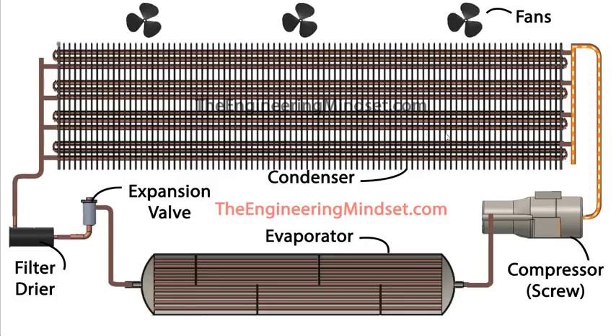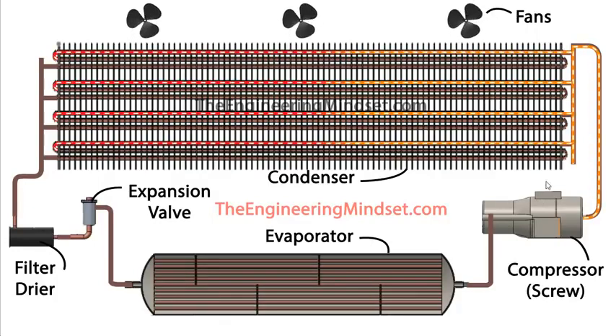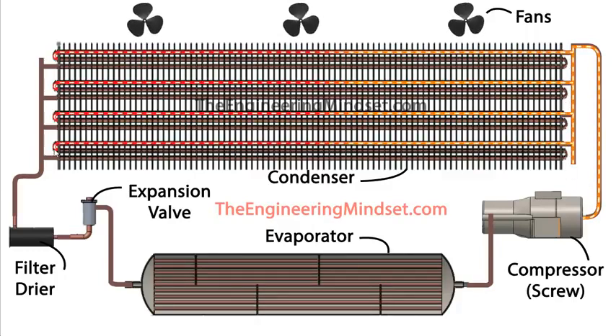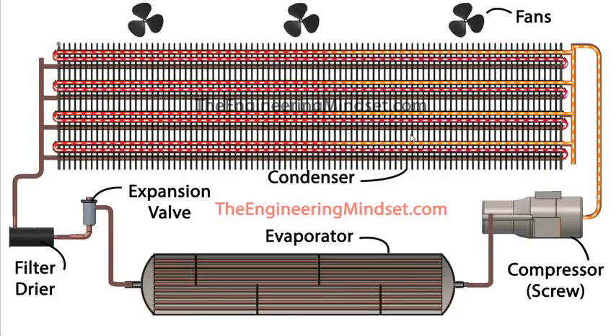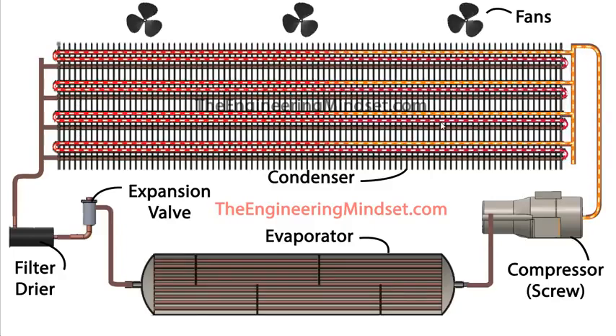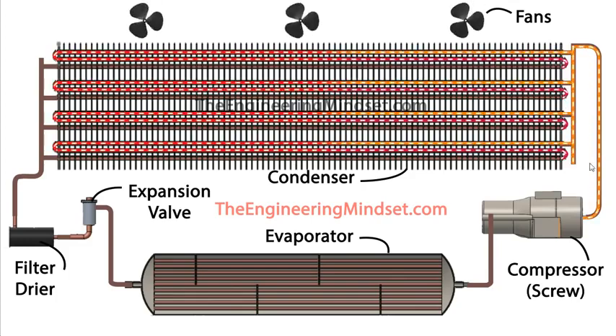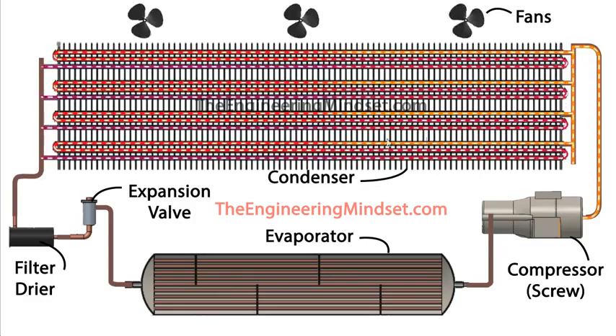These fins basically help to transfer that heat away from the pipes and out into the stream of the flow of air, so that increases the heat transfer surface area and the effectiveness of the heat exchanger. Now we can start to see some of that refrigerant as it's coming in off this distribution header and passing through the coil. You can see it's made its way around the first part there, and it's already started to cool down. It will then make its way into the second pass. So this is a 3-pass, 4-pipe condenser: 1 pass, 2 pass, and then the 3rd pass back and then towards the exit. And then finally you can see it's cooled all the way down, and it's made its way off into this collection header.